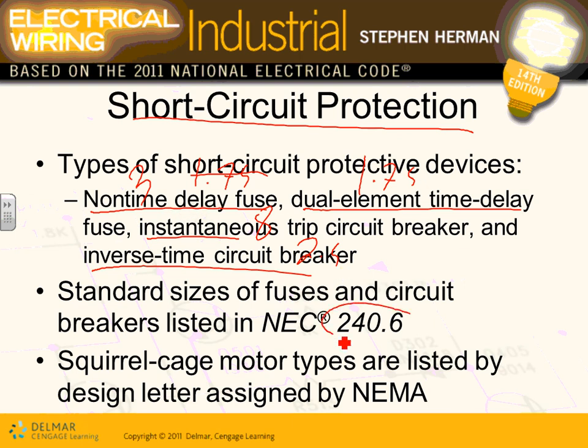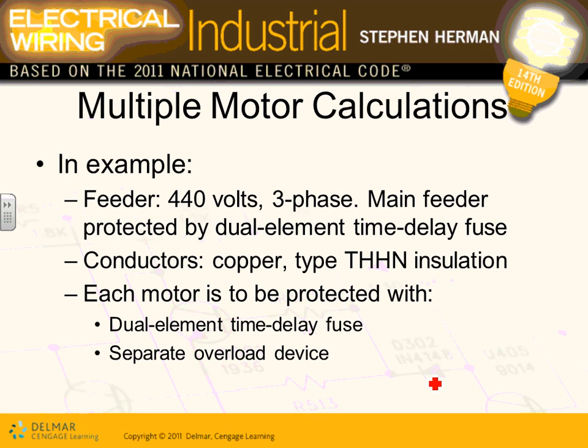You find the standard non-adjustable circuit breaker sizes from the NEC table, designated by the letter assigned by NEMA. Squirrel cage motors have NEMA design letters assigned to them. For multi-motor calculations, here's an example: calculating the feeder for a 440V three-phase system protected by dual element time delay fuses with THHN conductors.